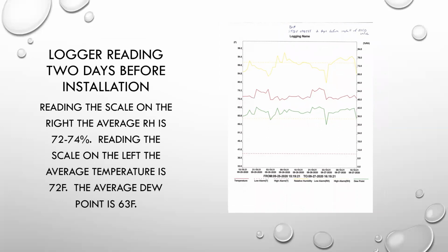The RH is the yellow line at the top. It's a little bit hard to see, but I can't change it because it's from the logger. If you look at the scale over there, this RH actually ran from 72 to about 74%. Sometimes it got a little bit lower, but if you look, they also had the cooling on quite a bit longer. But it ran from 72 to 74%, sometimes touching 80%, but that's where we're at. Now the temperature is the kind of reddish colored line running across the center there. That temperature averaged about 72 degrees, and the average dew point was around 63 degrees.